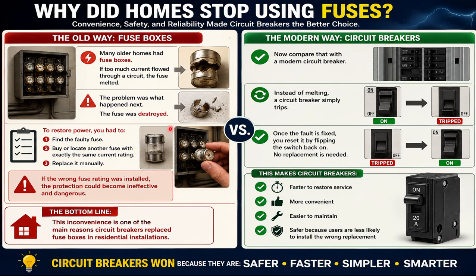And there was another kind of fuse, like the one we had where I was living, called a rewirable fuse. When the fuse blows, when the fuse element melts, you need to look for the same tin or the same lead of the same cross-sectional area as the one that just melted, and replace it. What happened a lot of times is that technicians will not find that exact one. Usually when the fuse melts, they don't even know the exact size of the fuse element or the exact metal that was there. So some people will just take copper conductors and put them across so that there's electricity again. Therefore, they have ruined the purpose of a fuse, because the fuse is there to protect. If the fuse element melts and you replace it with copper, definitely that protection is no longer there. So if the wrong fuse rating is installed, the protection could become inactive and dangerous. Exactly what I'm trying to say. And the bottom line is that with fuses, it is inconvenient.